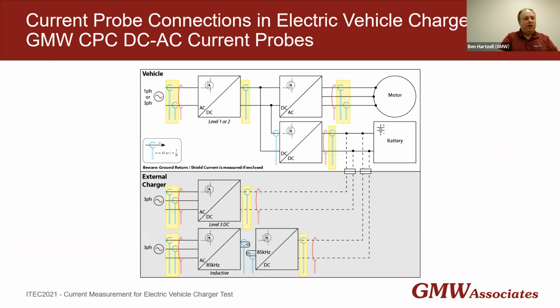So the CPC probe is good pretty much anywhere for quick diagnostics and long-term monitoring on almost any single conductor within the charging system. It's easy to open the jaws, and the compact size and light weight make it easy to install around existing cables and bus bars. Just a quick example of that.